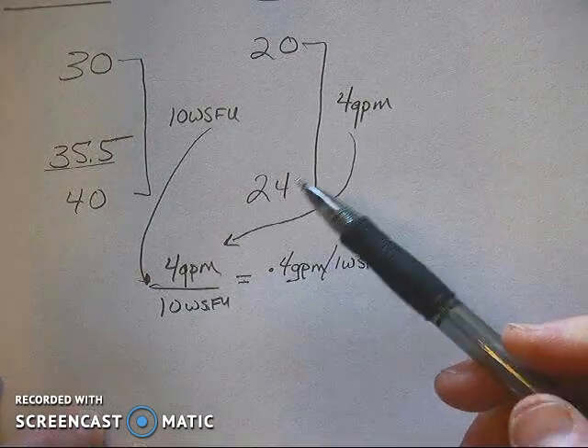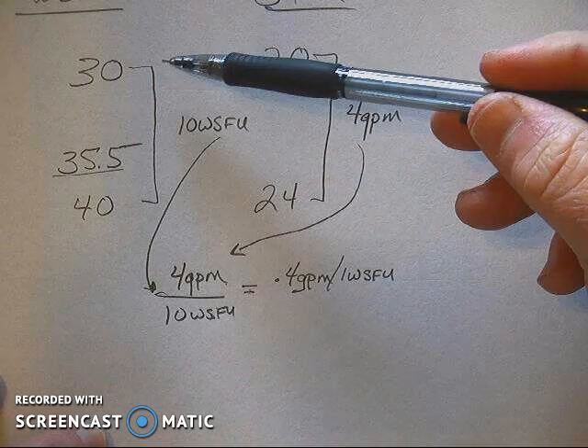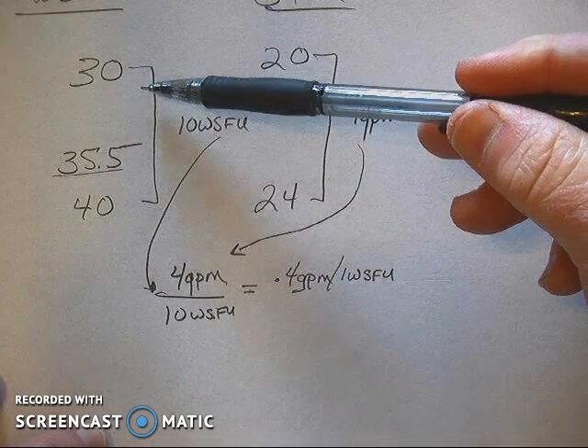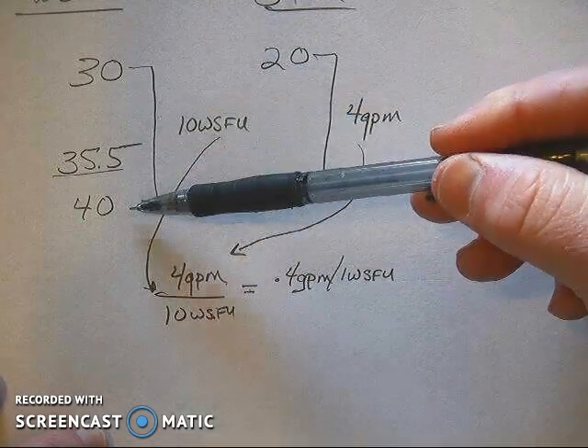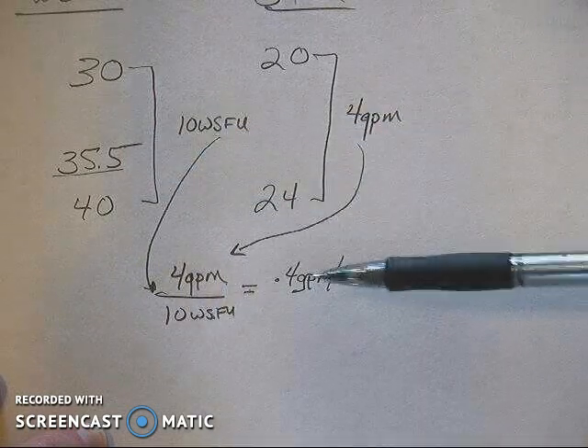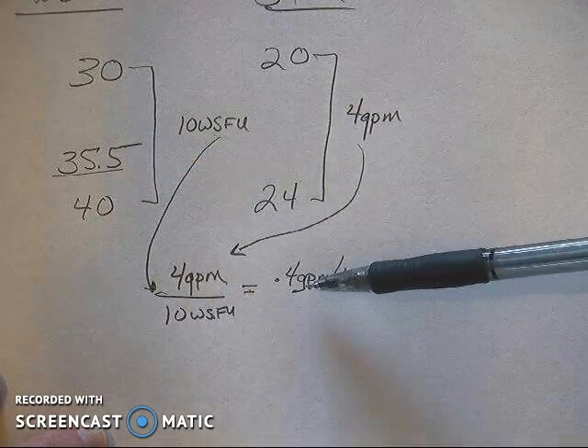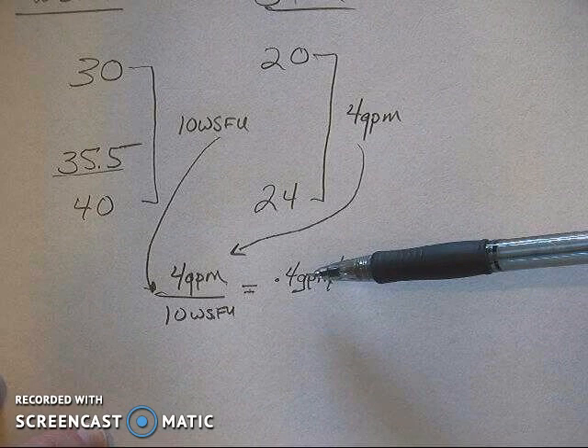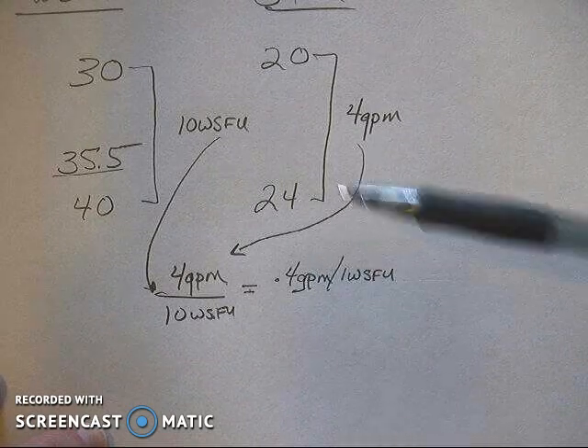So for every WSFU that I go up after 30 or come down from 40, the gallons per minute will be 0.4 gallons per minute for every WSFU.